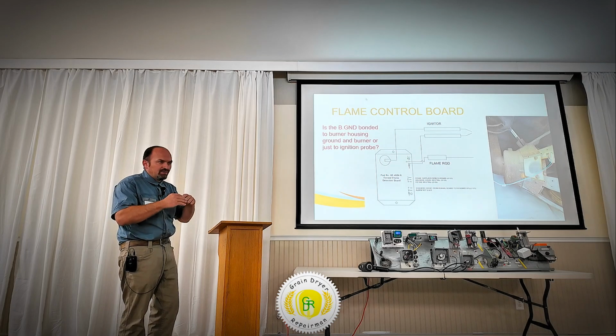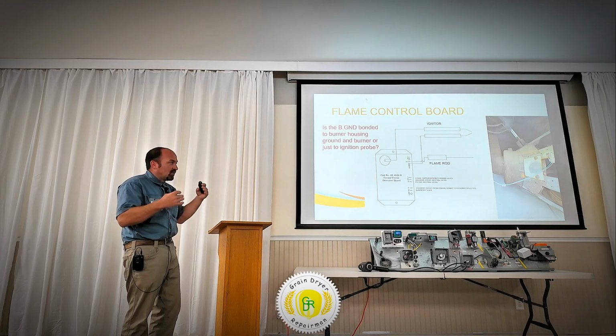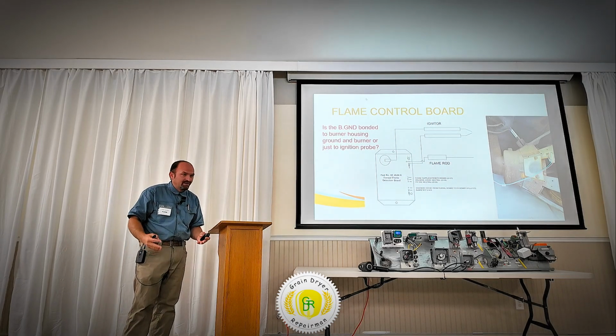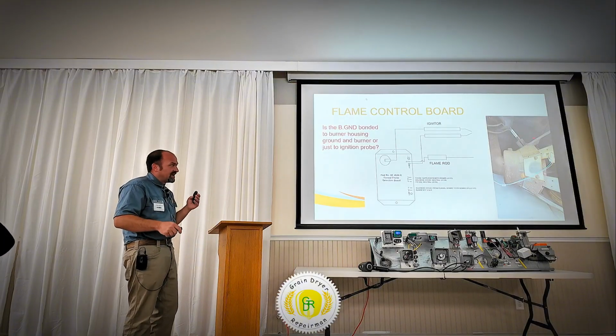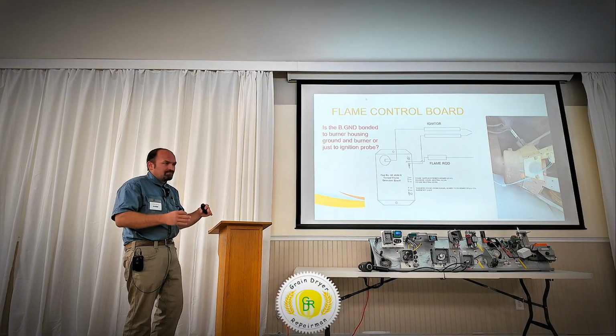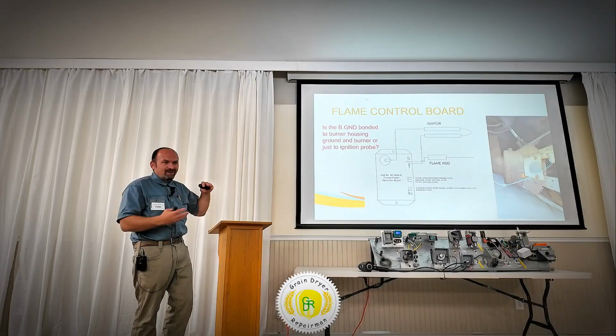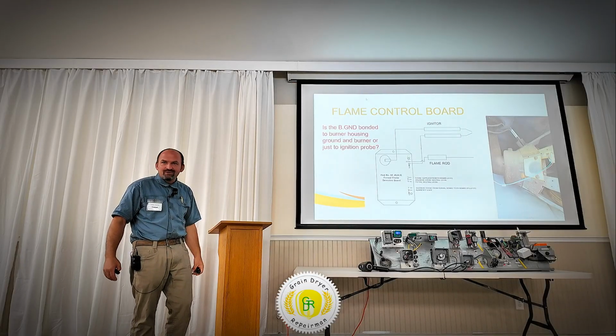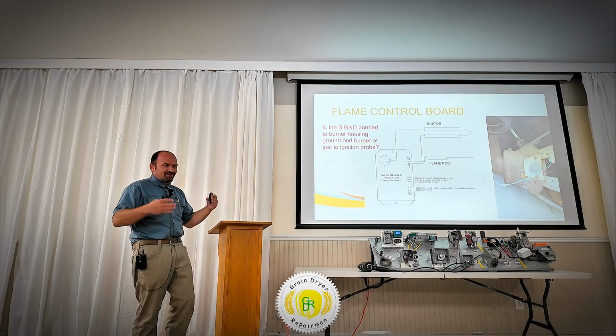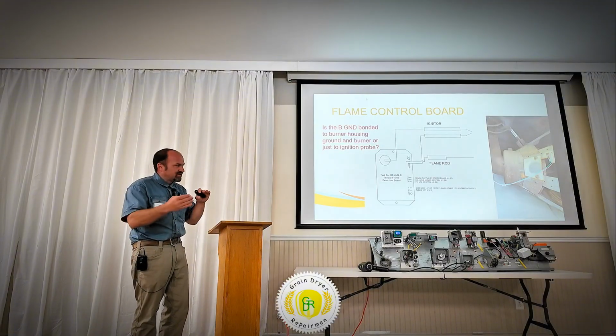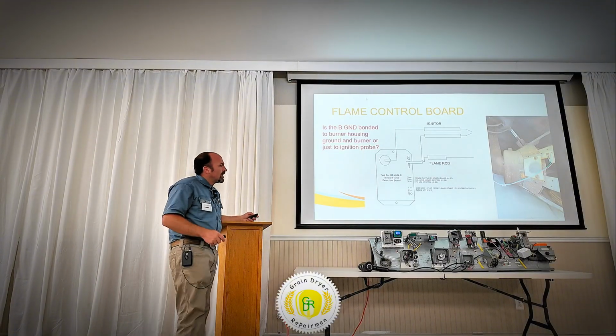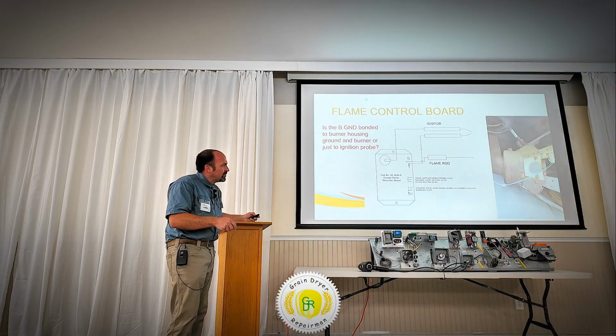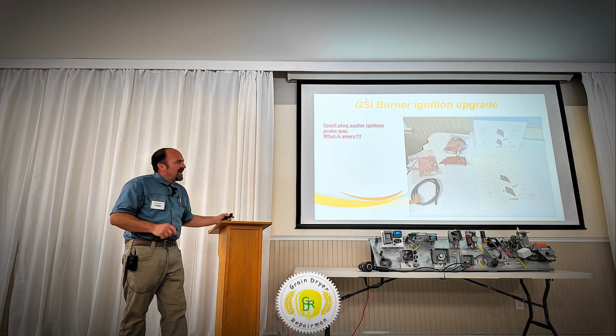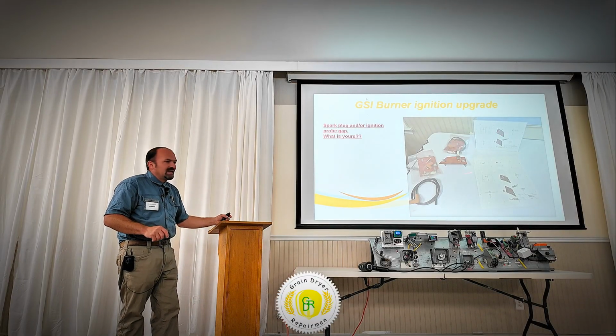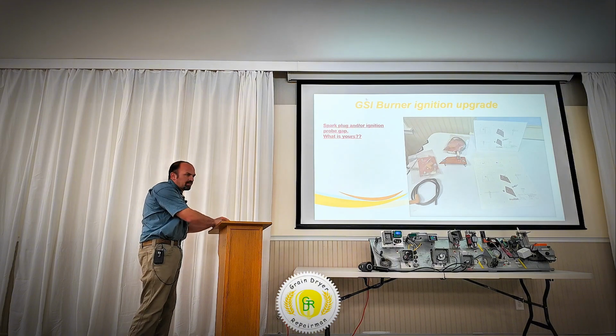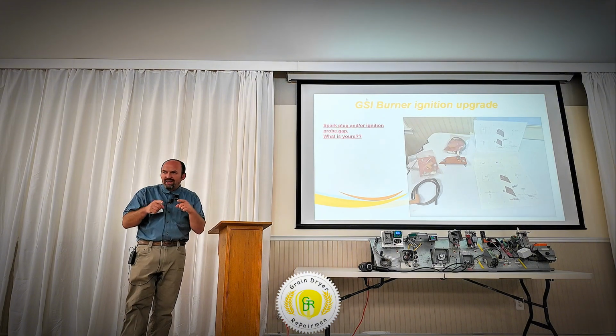That's something that I do if I'm going out, especially to a natural gas burner, a Starfire natural gas burner. I'm putting a second flame rod on. I'll put a second flame rod in a brand new dryer before I start it the first time, because it's just going to eliminate headaches down the road, because you're going to run into those issues. The other thing, we'll get to that. Okay, this option of eliminating those flame probes. Now, those flame probes are a pain in the neck.